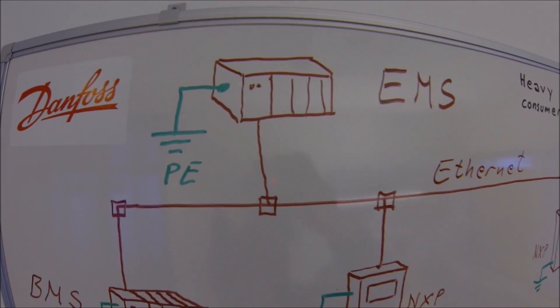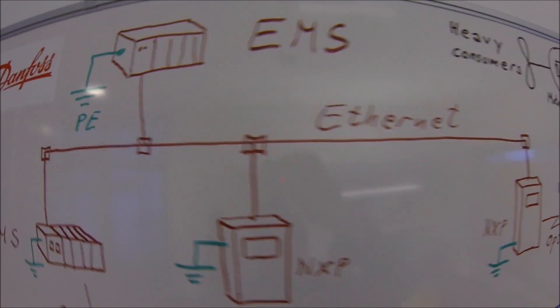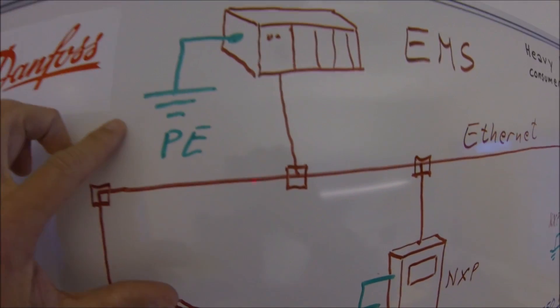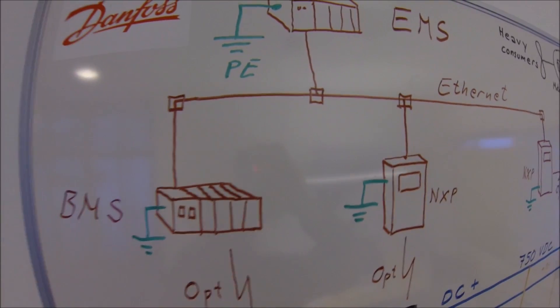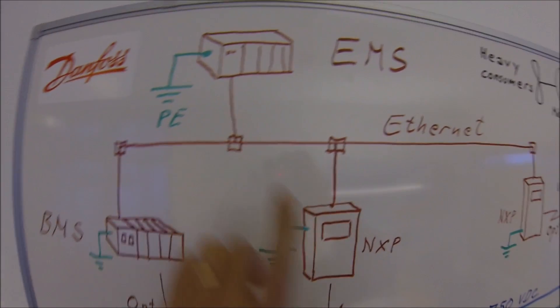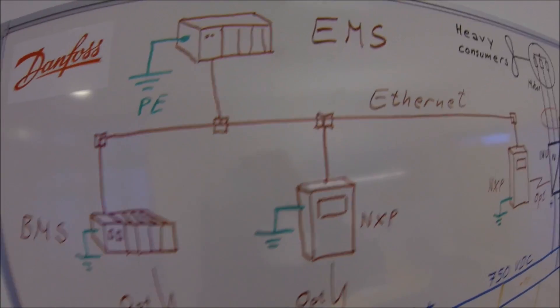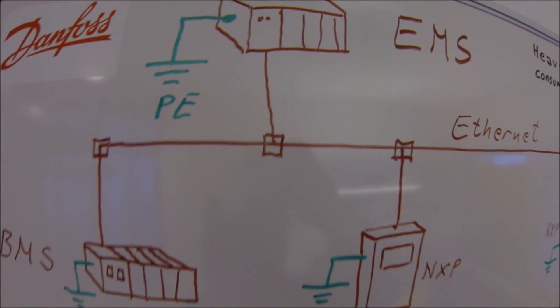These PLCs and Ethernet systems usually have a connection to the protective earth. It's common practice to have the zero voltage at control voltages and bus systems connected to protective earth.